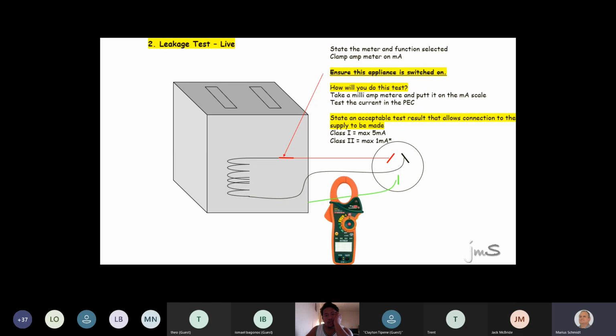Right, now I'm going to ask you guys this. Have you guys ever heard about a PAT tester? You know what's a PAT tester? What does PAT stand for? Portable Appliance Tester. It's a special tester where you take your plug, you plug it into that tester. The tester is plugged into the wall and you press test. It will check the ohms and it will check the insulation resistance and it'll tell you if it's a pass or not. And what you don't know is it actually measures if there's any current flowing in the earth. If there's no current, it will tell you pass. If it's a fail, it means it will pick up current in the earth. Happy?